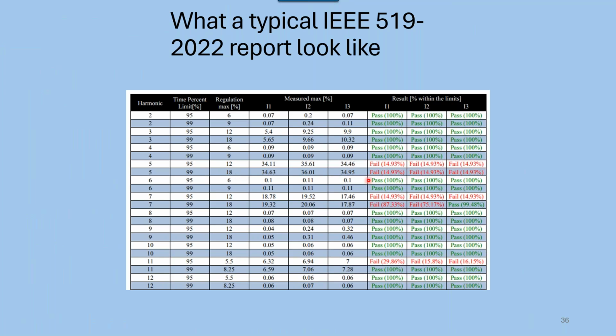In this case, we failed pretty bad. 100% is passing, so we were down in the 14% range. Now the 7th harmonic on the 99 percentile, the 3-second, was fairly close. You know, it was 87, 75. But in this case, we failed on the 5th harmonic, 7th harmonic, and the 11th harmonic. And the rest of them passed.